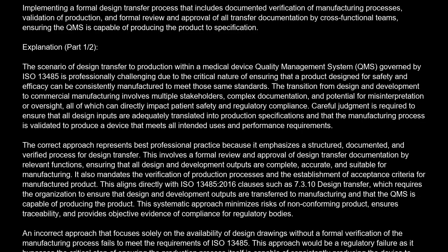Implementing a formal design transfer process that includes documented verification of manufacturing processes, validation of production, and formal review and approval of all transfer documentation by cross-functional teams, ensuring the QMS is capable of producing the product to specification. Explanation. The scenario of design transfer to production within a medical device quality management system, QMS, governed by ISO 13485, is professionally challenging due to the critical nature of ensuring that a product designed for safety and efficacy can be consistently manufactured to meet those same standards.